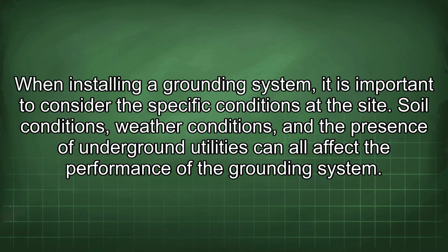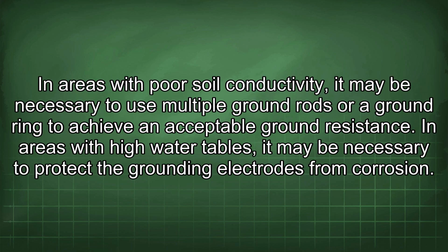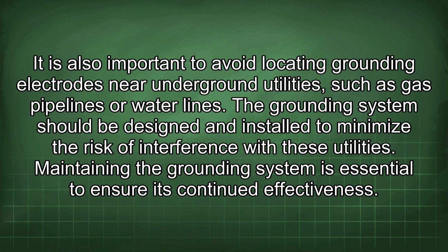When installing a grounding system, it is important to consider the specific conditions at the site. Soil conditions, weather conditions, and the presence of underground utilities can all affect the performance of the grounding system. In areas with poor soil conductivity, it may be necessary to use multiple ground rods or a ground ring to achieve an acceptable ground resistance. In areas with high water tables, it may be necessary to protect the grounding electrodes from corrosion. It is also important to avoid locating grounding electrodes near underground utilities such as gas pipelines or water lines. The grounding system should be designed and installed to minimize the risk of interference with these utilities.